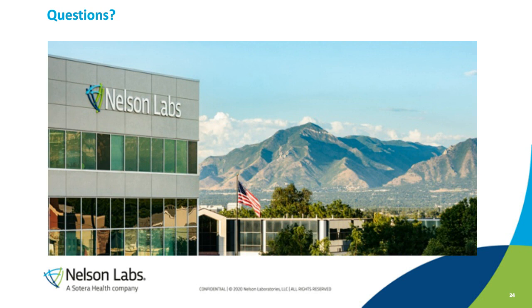No, it's pretty much that. The only other thing is you really want to be able to justify that whatever you're not including in your coupon, one, doesn't impact the processing, like Matt said, but also could not ever touch liquid of some type and then get back into the patient, even in a failure scenario. But if you can replicate the processing and justify that that material would never come in contact with the patient, then we would not want to include it in the coupon, because then you're just including compounds or biocompatibility risks for something that does not have patient contact.